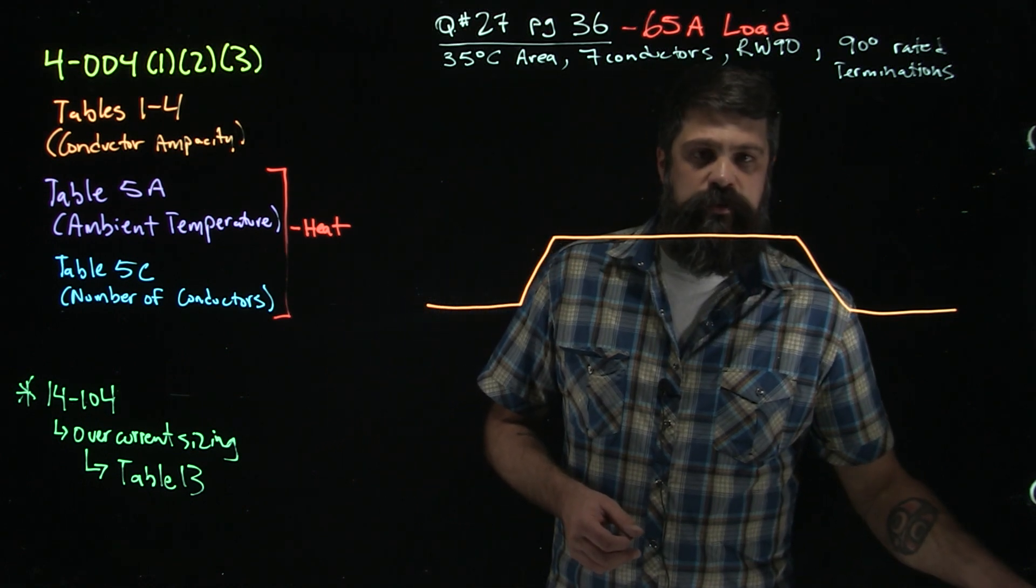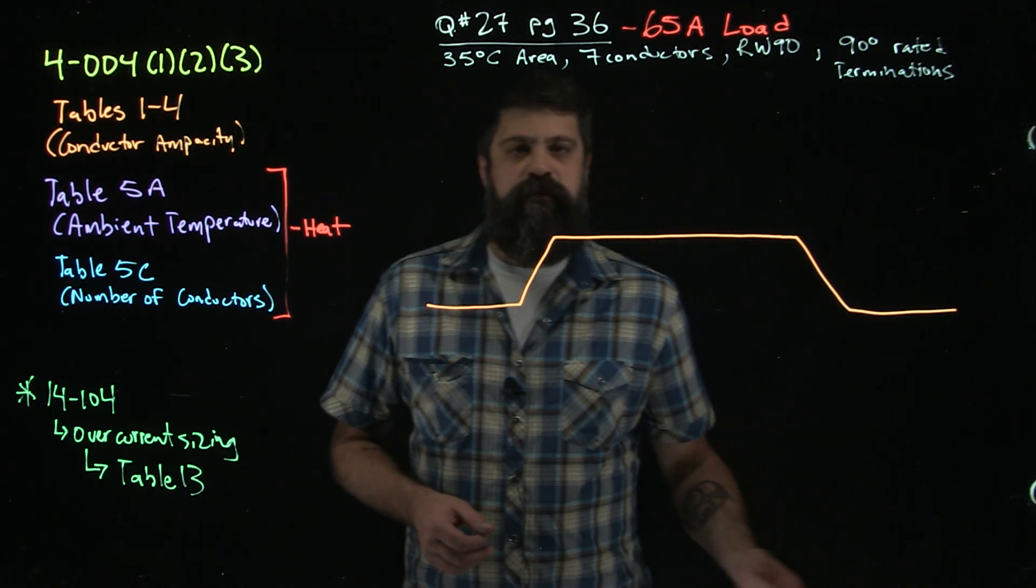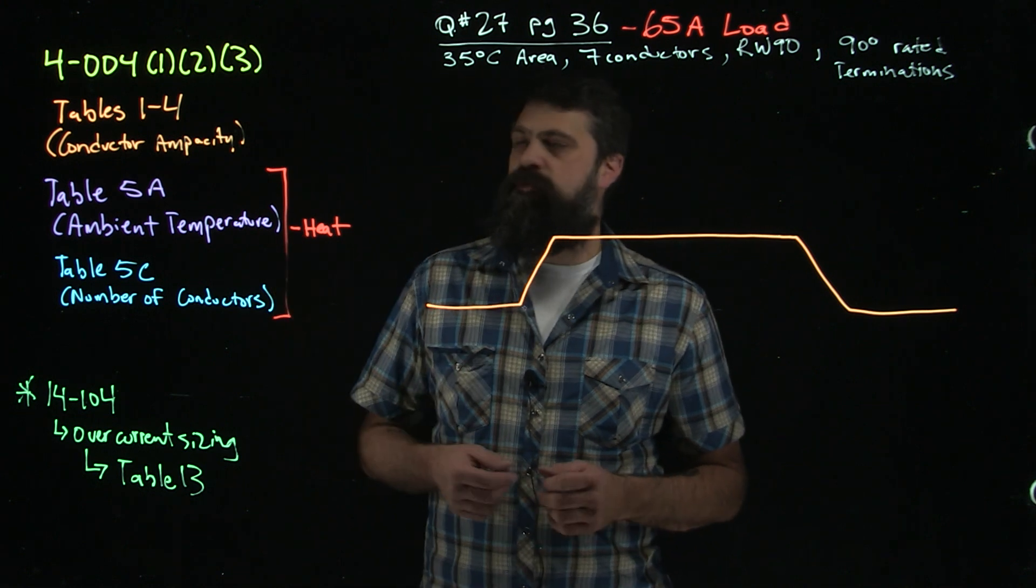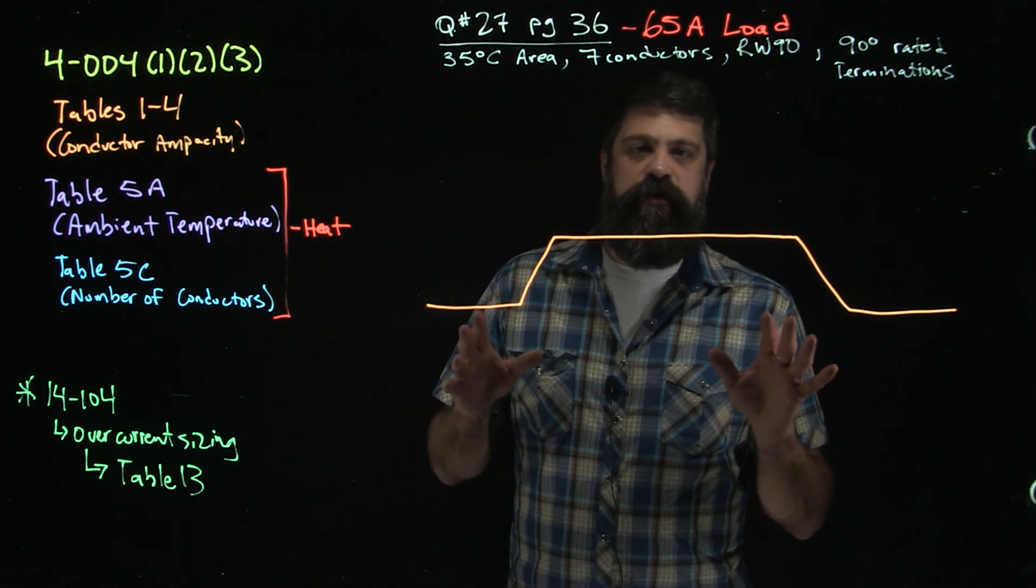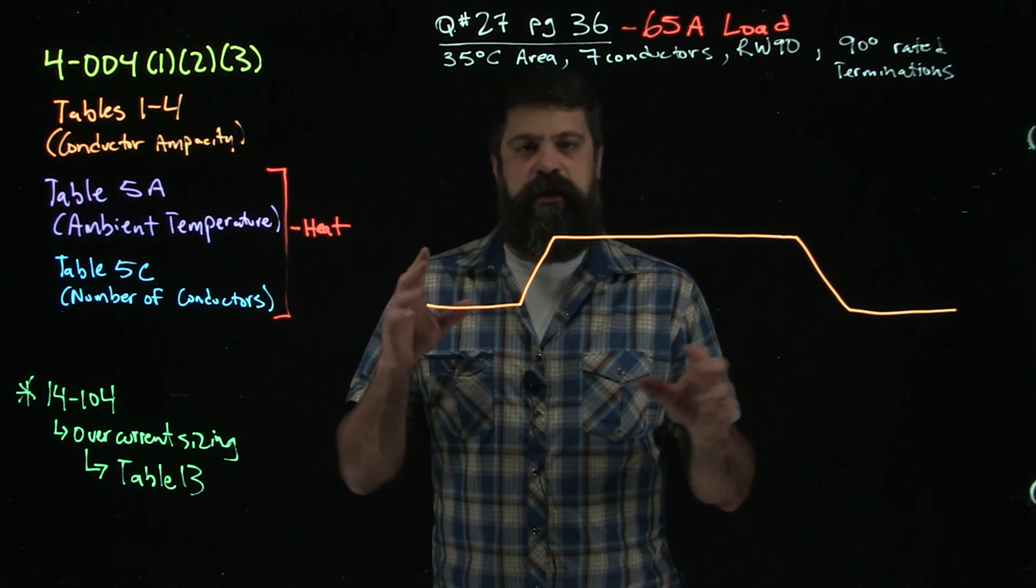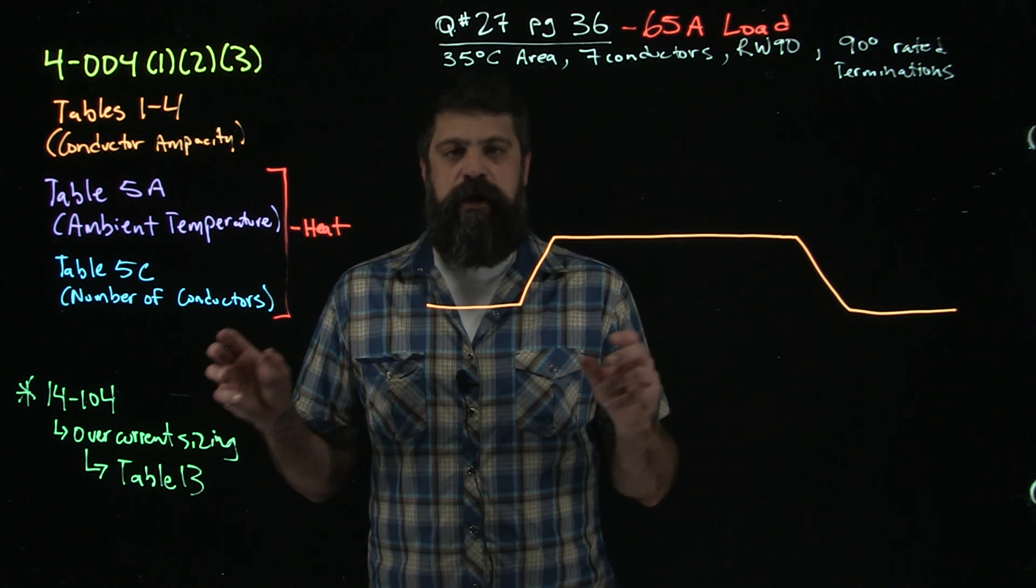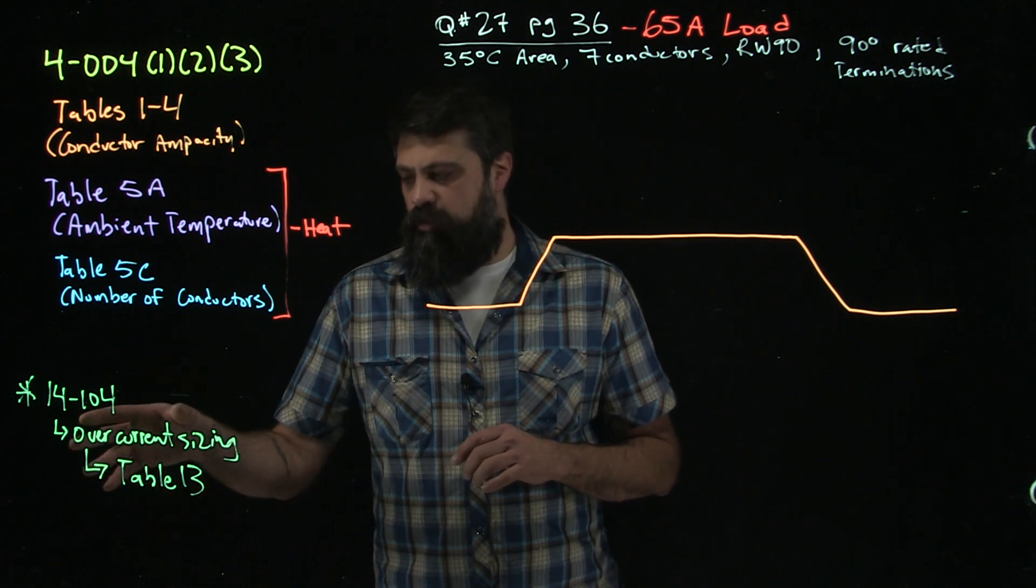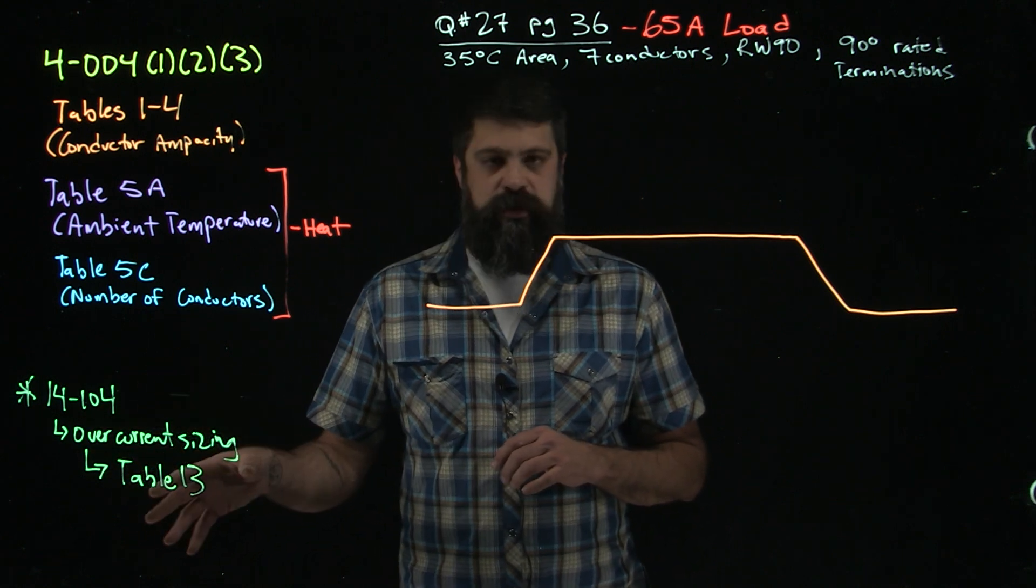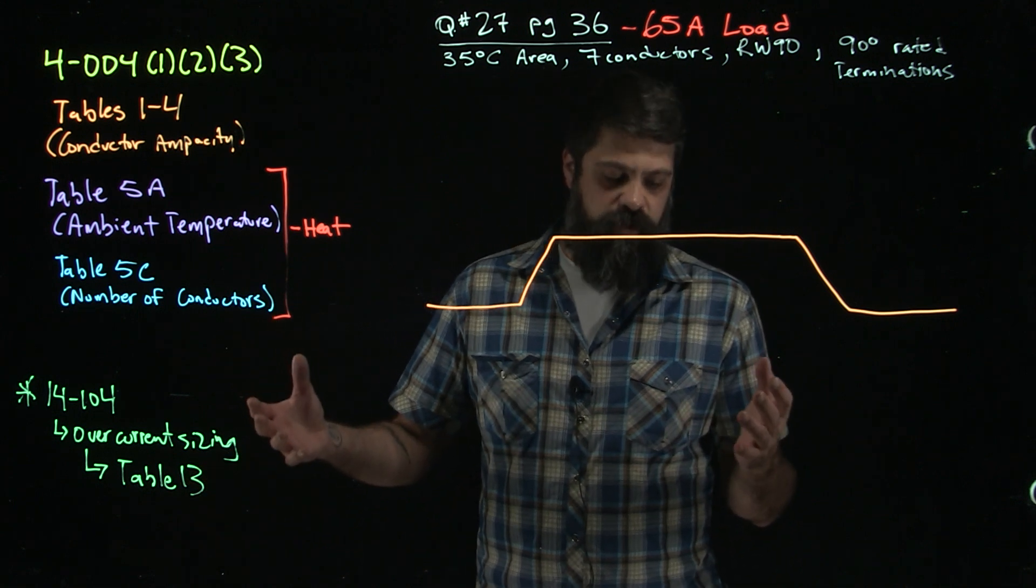Hey everybody, I just want to go through another example of wire sizing from rule number 4004. This time we're going to throw a couple different things into it to get our feel for tables 1 to 4. We're also going to size a breaker based on rule 14104. Rule 14104 tells me how to size an overcurrent, then takes me to Table 13 where I pick my overcurrent out.